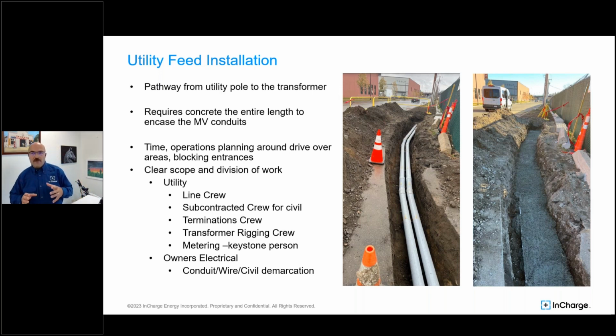A lot of times this is out of your control because once the utility is involved, they have their own subcontractors, and they are a very layered, bureaucratic type of organization. So you have a line crew, they have a subcontracted crew that does some of the civil work or the poles. You've got one crew that terminates the wires on the transformer on the pole or in the switch cabinet. Then you've got the transformer rigging crew that's going to come out and drop the transformer in place.